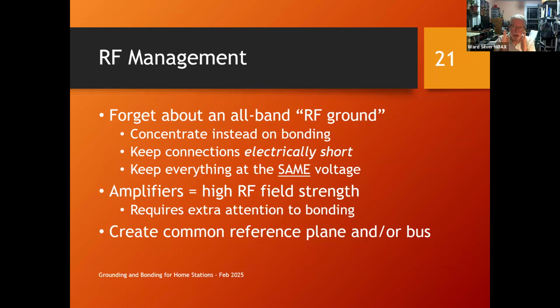Keep your connections electrically short, not big loops of wire. Don't coil up your connections. If you can connect stuff with a simple strap to a pipe or your bonding plane, you're in much better shape than having wires running all over the back of your equipment. The goal is to keep everything at the same voltage with low inductance, electrically short connections.